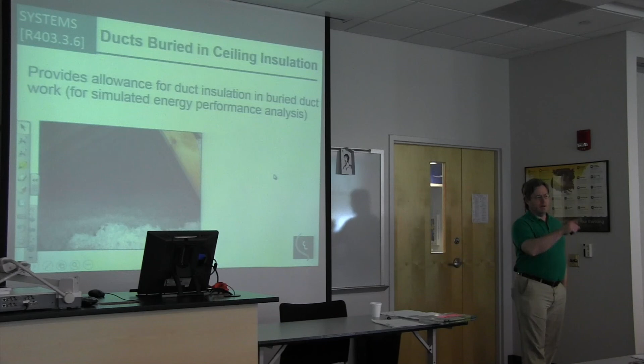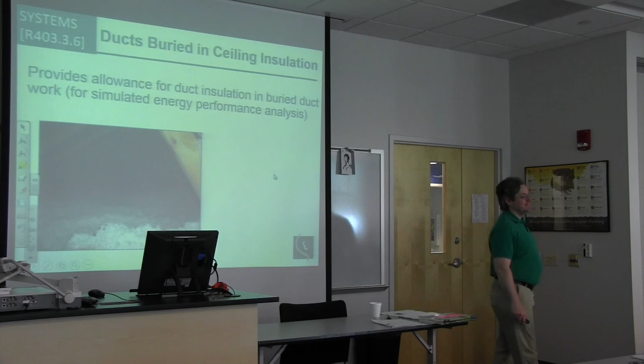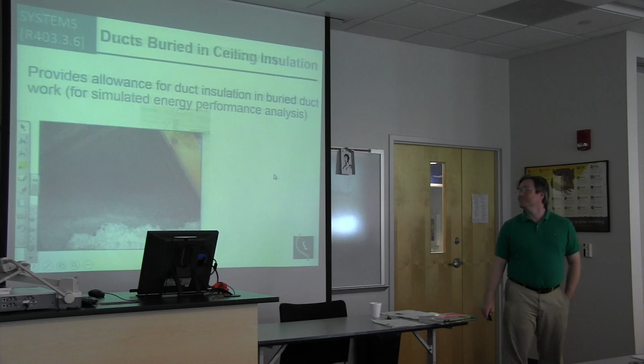Ducts fully buried. There are now provisions for how you treat ducts that are fully buried. Fully buried in this case means if it's R49, you have to have R49 above that duct. So fully insulated. Then if they're fully buried, they're not considered in the unconditioned space, so they don't have to have a blower test? If they are fully buried, no, it's not that. What it does is allow those to be modeled better if you're doing energy modeling. Before, even if you fully buried that duct in R49, the energy model would reflect an R8, because that's what's on the duct. So this kind of fixes one of the problems in the software. And that's an issue too.